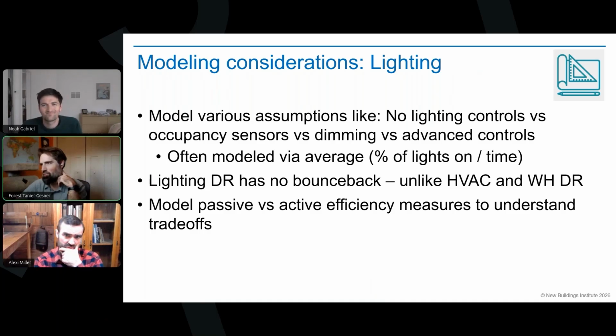So the lighting controls, it's just understanding what your lighting system's capable of and how much you can actually dim down. The percentage of your overall lighting load that is going to be tied to this system is a key first part. And then the actual scheduling of it is relatively straightforward. It does have some interactivity with your heating and cooling system. Ultimately, it's to the better with your cooling system, because as you dim down the lighting system, you're reducing the load to the space. It does add a little bit of heat load to the space during a winter event, but typically your winter peaks are going to be in the late evening hours or early morning, and so it tends not to be much of a driver. So that interactivity is not necessarily a detriment to you.